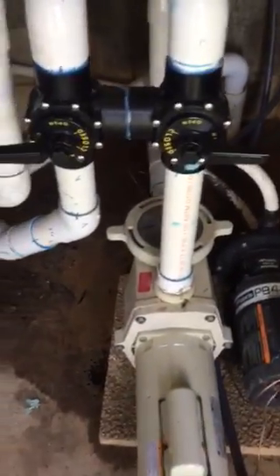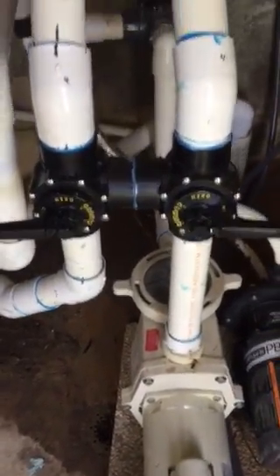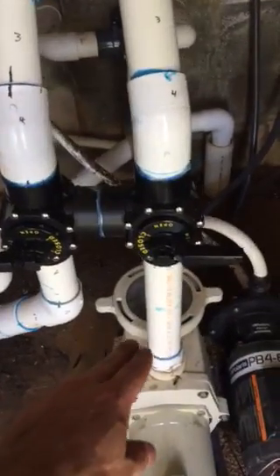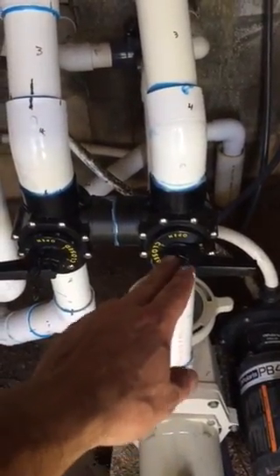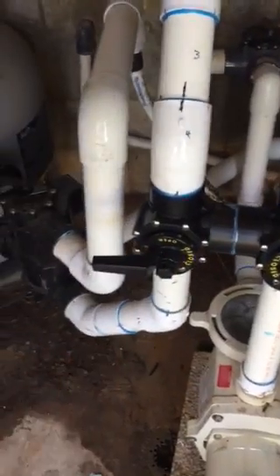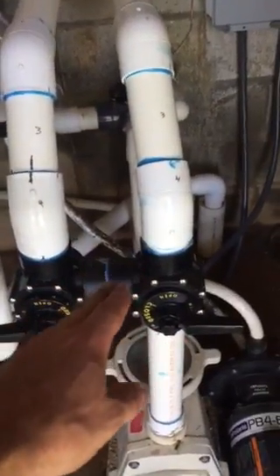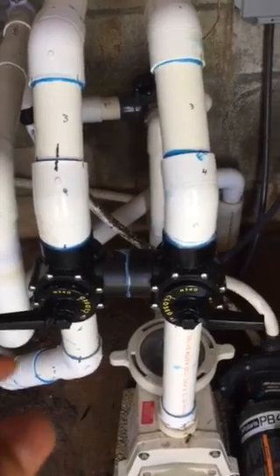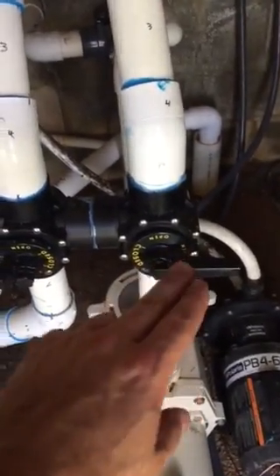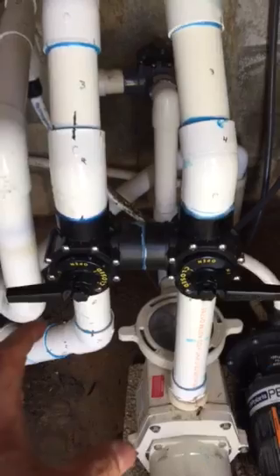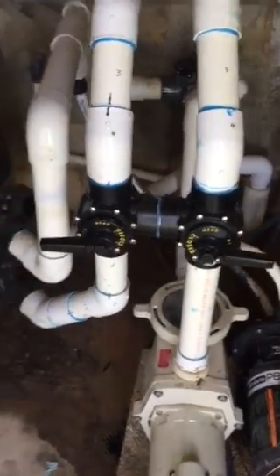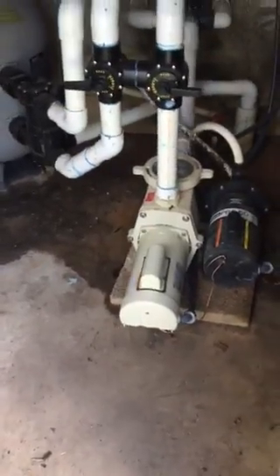And we have these three-way valves here, so if the water for any reason needed to be diverted to the sand filter, back to the pool, and bypass the condenser, then there's an option for that, and we would just flip those valves around. So with that being said, I'll show you what we got on up top of the condenser.